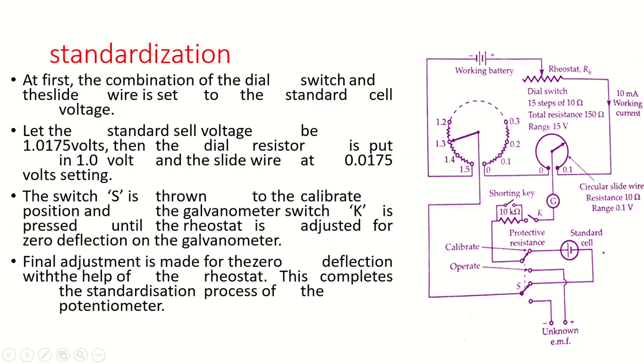The first procedure, before finding the unknown EMF, is standardization of the potentiometer. Standardization means comparing the output of the potentiometer with a known value of EMF to check whether the results match. If not matching, adjust the rheostat or dial position to get the correct value. First, the combination of dial switch and slide wire is set to the standard cell voltage — for example, 1.0175 volt.